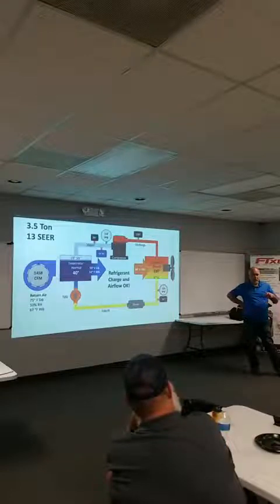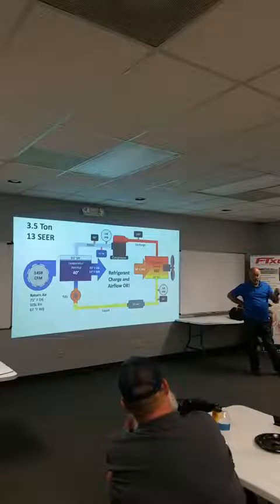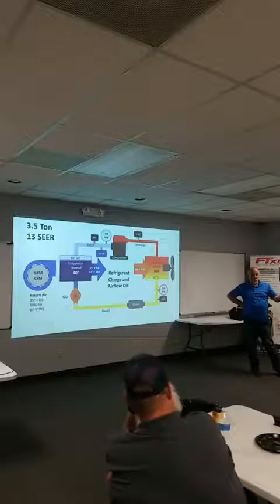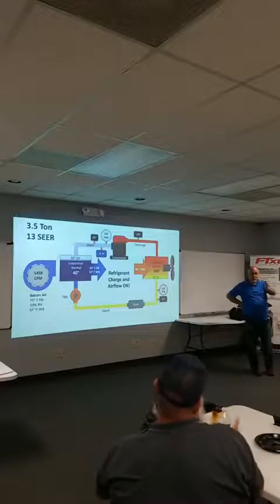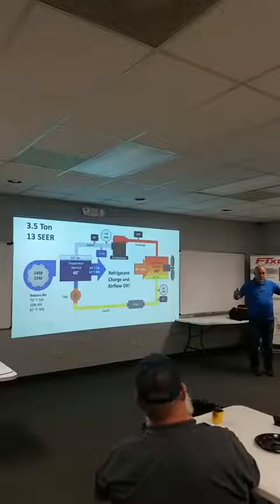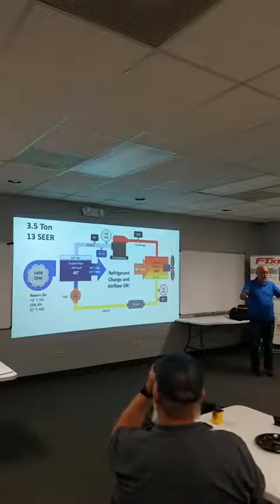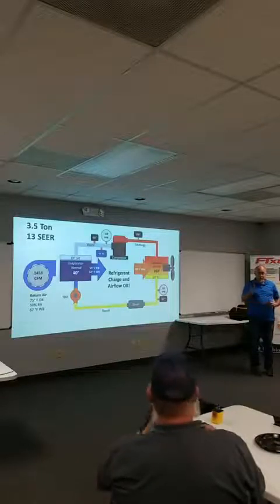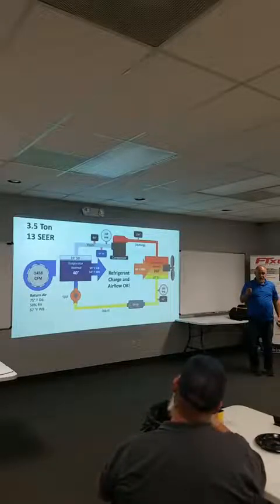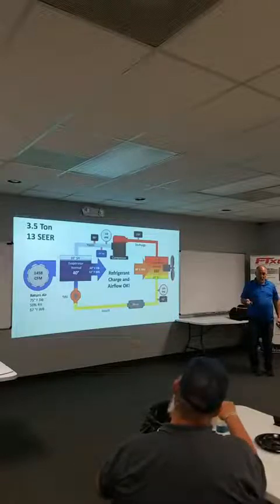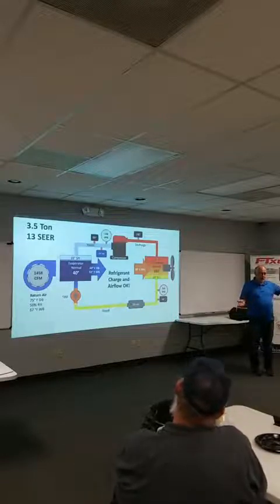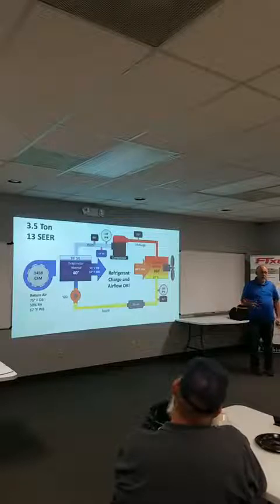Well, it ended up that they told him, well, you gotta have 12 degrees of superheat at the compressor. So the guy just kept opening up the thermostatic expansion valve, opened it up so far that it was no longer metering anything. And all the refrigerant was flashing in the suction line. So instead of flashing in the evaporator, it's producing no cooling, and it's flashing in the suction line, huge long suction line. So I start cranking down that TXV on that thing till I get the superheat at the evaporator coil. And I'm picking up a lot of superheat up to the compressor, right? Now I'm running like, I don't know, 20, 30 degrees of superheat at the compressor.